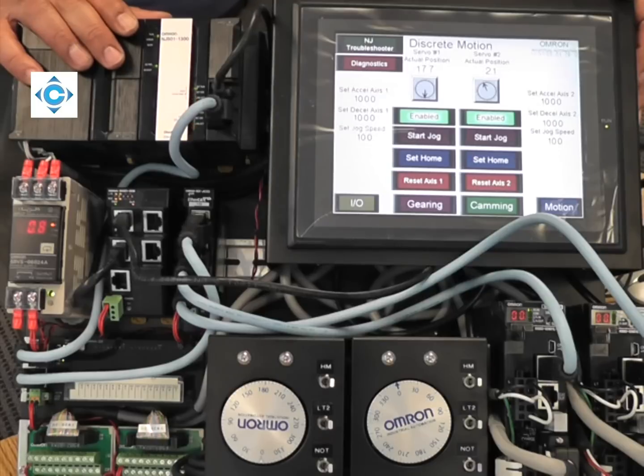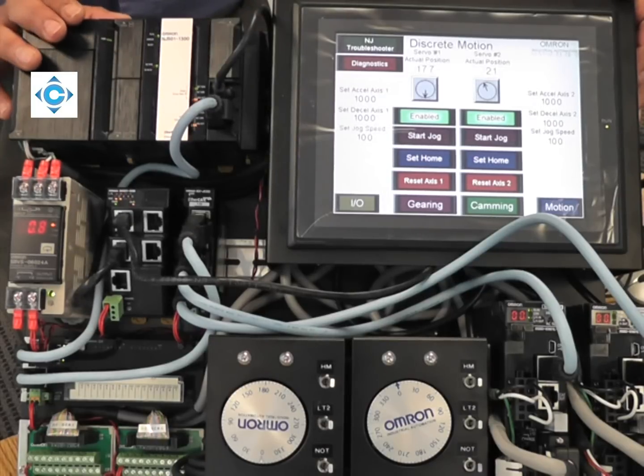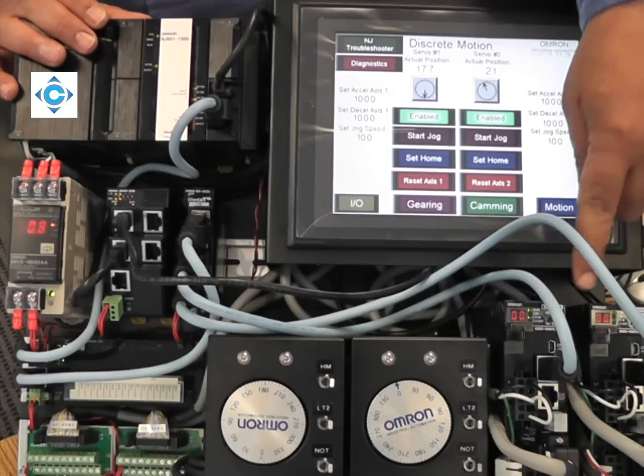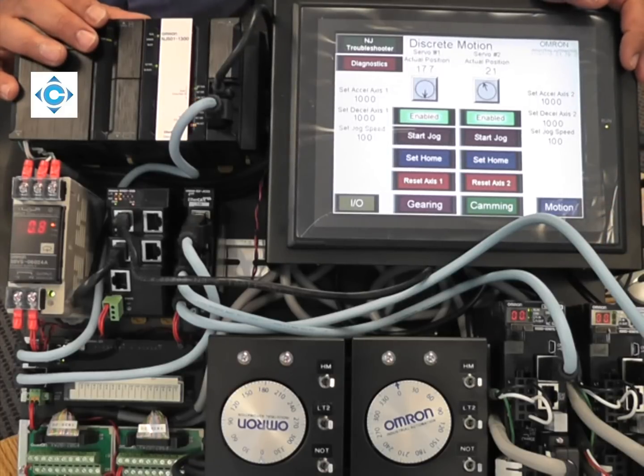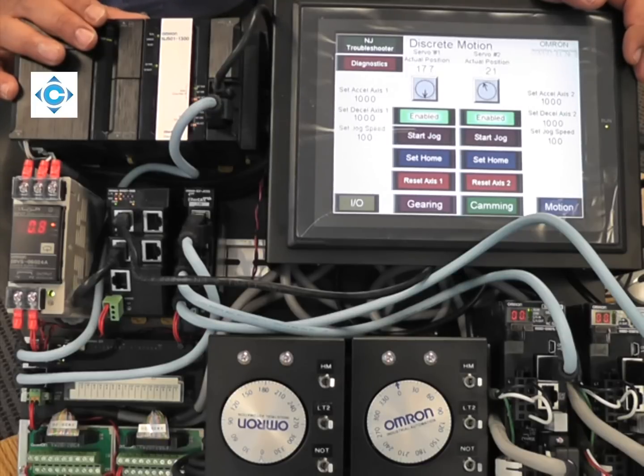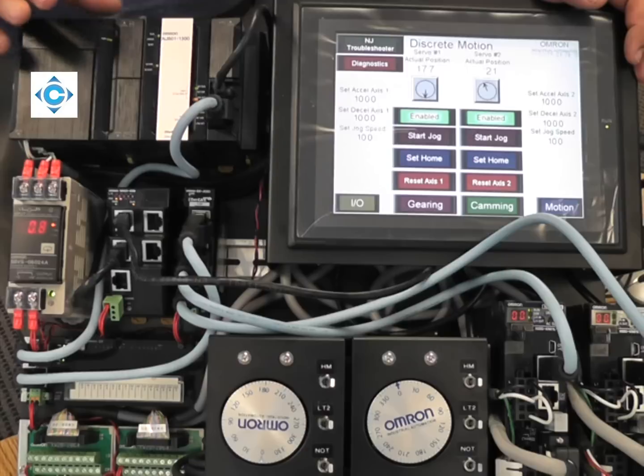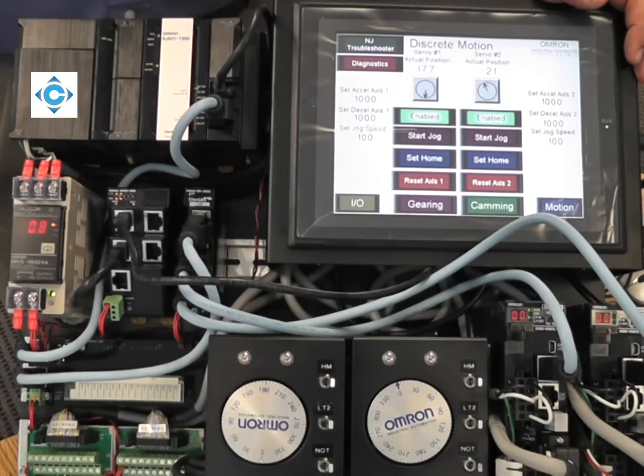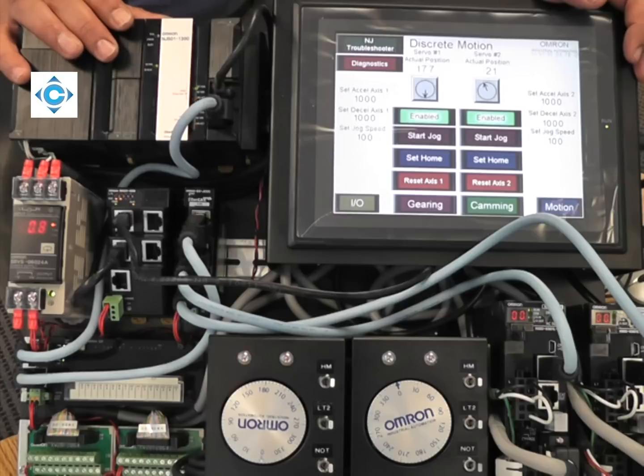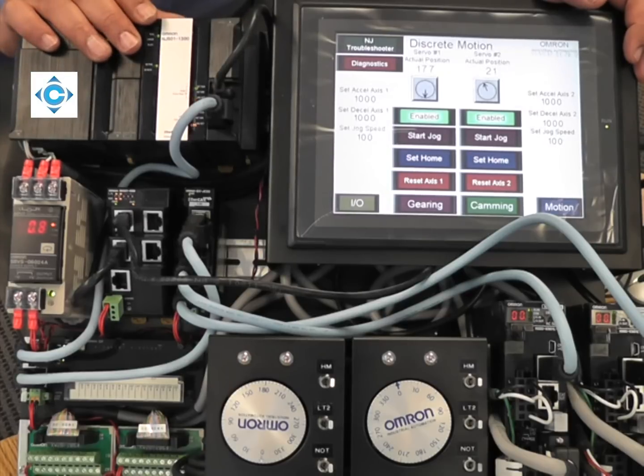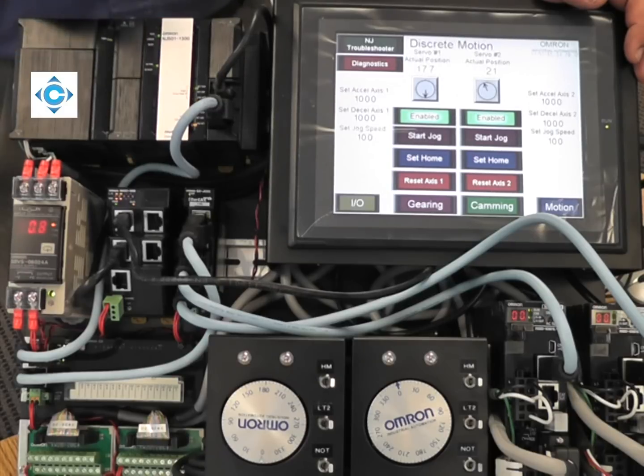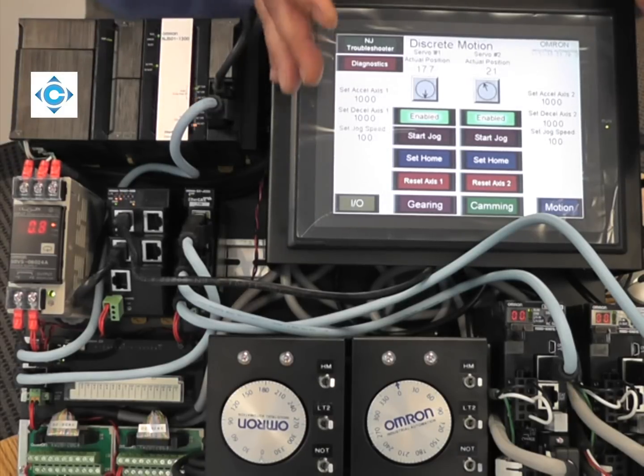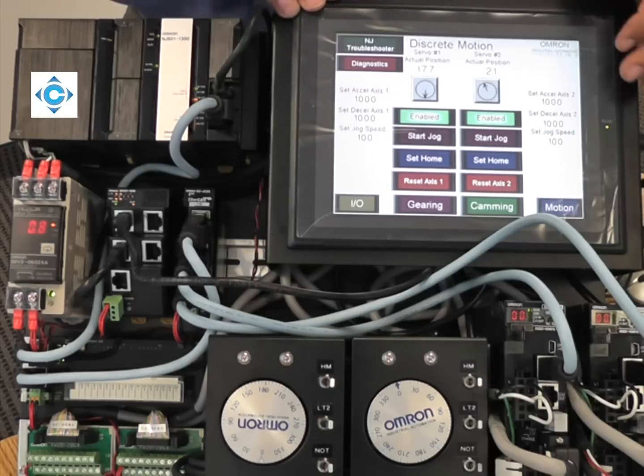Other discrete motion that we're not showing here that the NJ can do through the G5 servo: we have high-speed registration, and each G5 has two built-in high-speed registrations done by hardware in a few microseconds. We can do CAM output where the NJ can fire an output in a specific position, and we can do interrupt feed. We can control position, velocity, or torque as well.